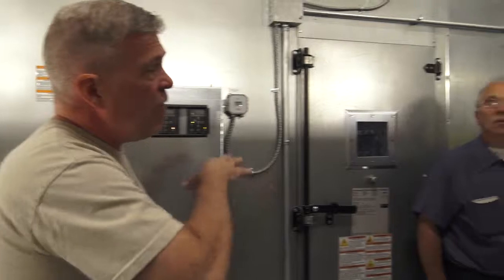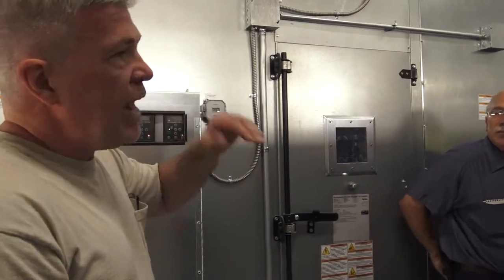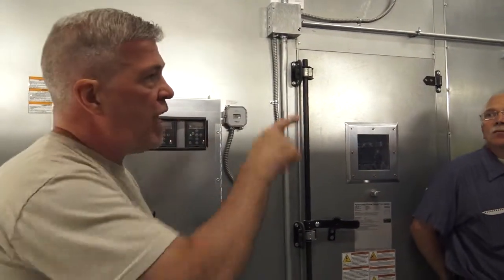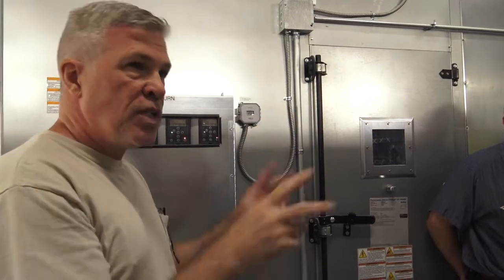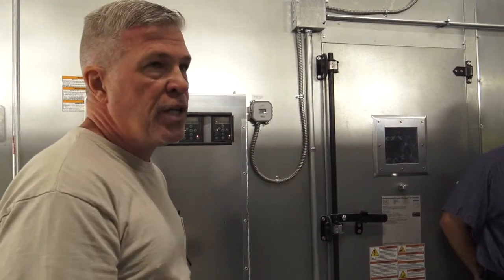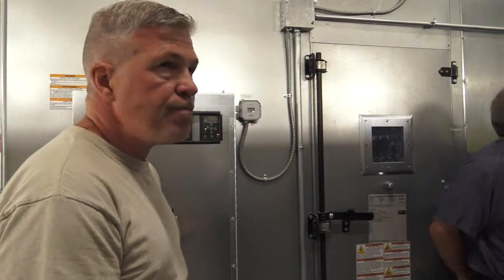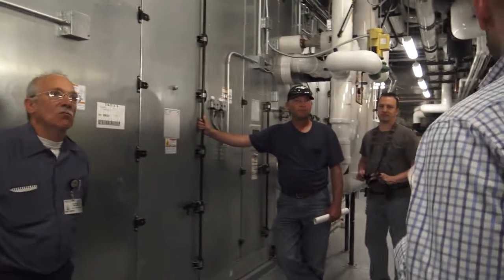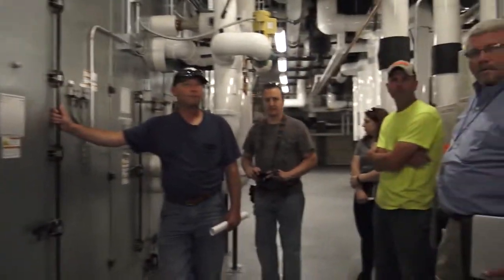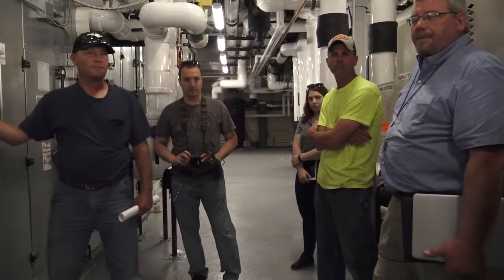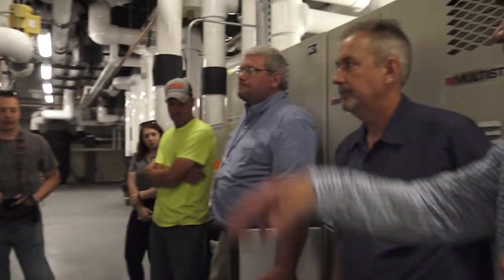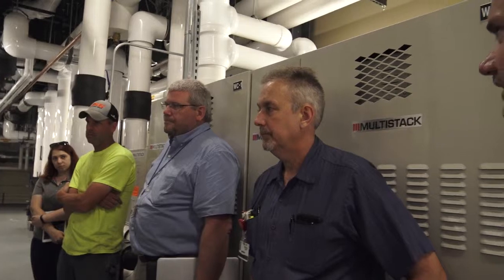If you say, well, at 3 inches I want to change them, you can actually set up an alarm on those that says when it's at 3 inches, it tells you, and then you know to change it. Makes sense to do that just in case outside of your PM you had an anomaly, like cottonwood released all its stuff and now you've got buildup.